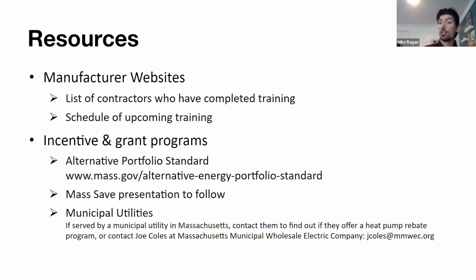So for situations like that where you have a zone served with a fan coil that doesn't have an outside air integration, you could still integrate that with the space, whether that is an occupancy sensor, whether that's literally by detecting a person, whether it's by CO2 levels for demand control ventilation, et cetera. So these are all options for tying in these fresh air applications to heat pump technology.